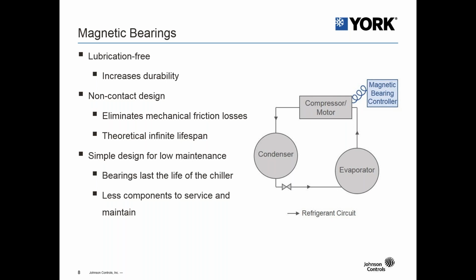When you look over to the schematic of the chiller, you can see the entire system for lubrication is removed. So it's a very simple design from a maintenance standpoint, and the bearings are designed to last the life of the chiller with no scheduled maintenance or routine tear downs to check to see if there's any wear or potential failure coming in the near future. So fewer components essentially leads to less service and less to maintain.